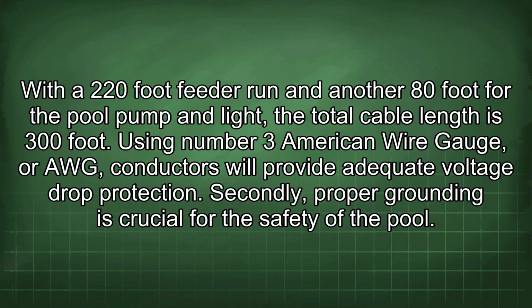With a 220-foot feeder run and another 80 feet for the pool pump and light, the total cable length is 300 feet. Using number 3 American Wire Gauge, or AWG, conductors will provide adequate voltage drop protection.